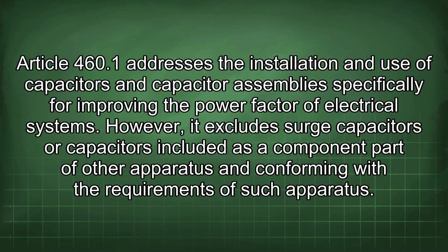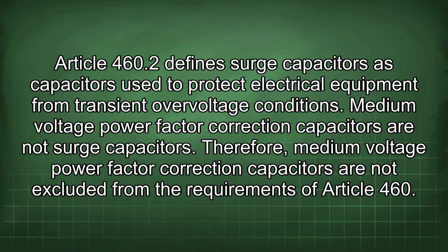Article 460.1 addresses the installation and use of capacitors and capacitor assemblies specifically for improving the power factor of electrical systems. However, it excludes surge capacitors or capacitors included as a component part of other apparatus and conforming with the requirements of such apparatus. Article 460.2 defines surge capacitors as capacitors used to protect electrical equipment from transient overvoltage conditions.